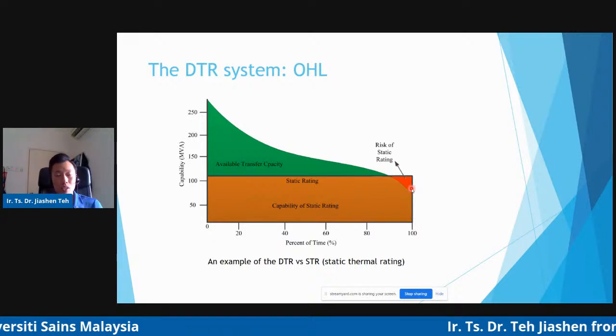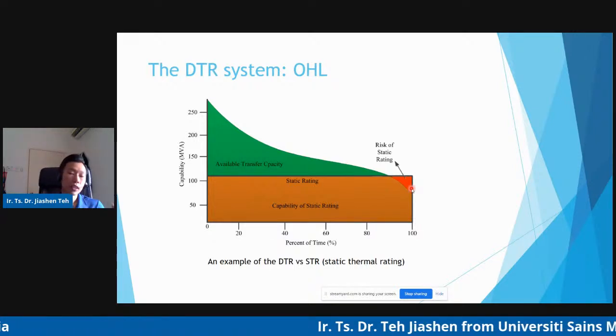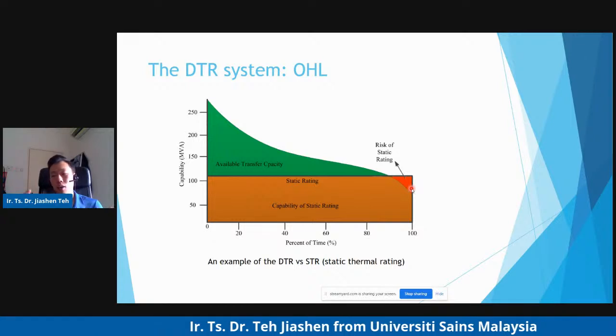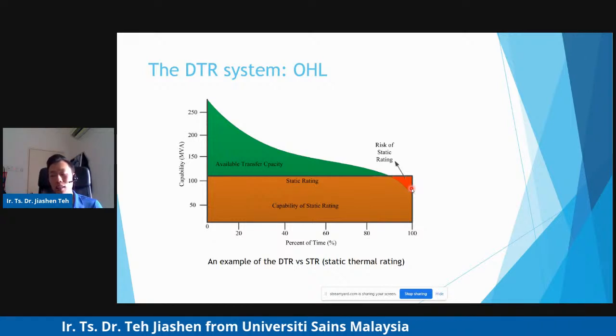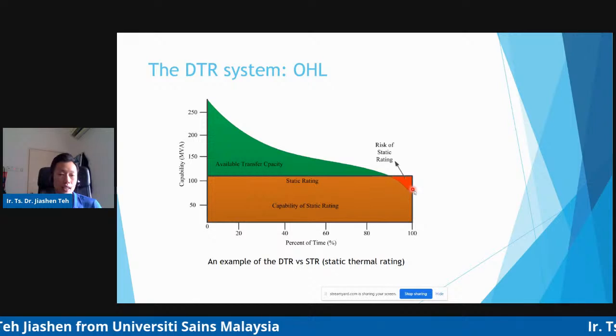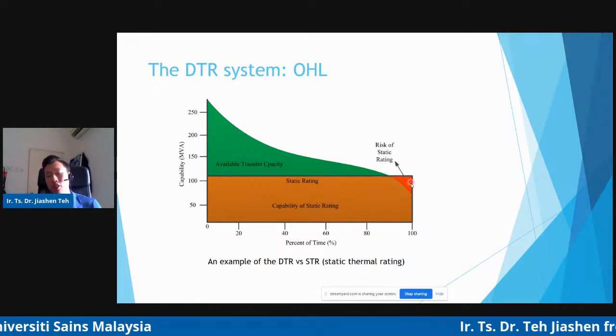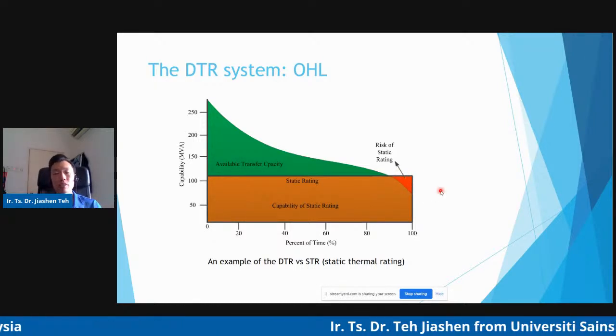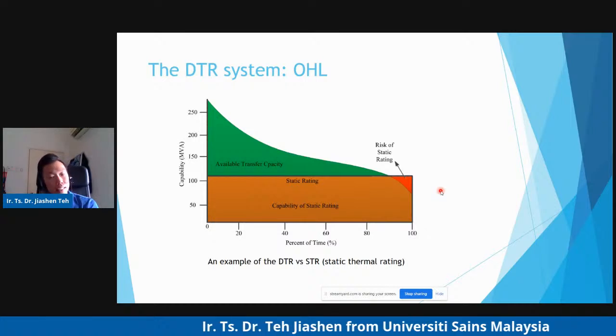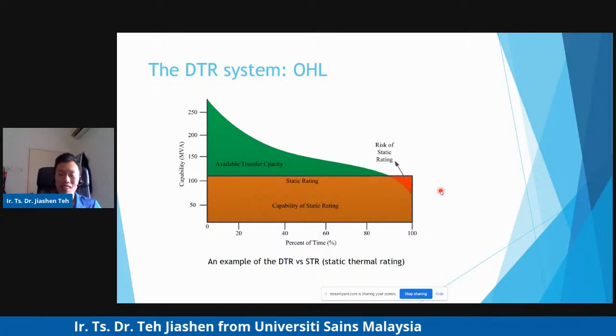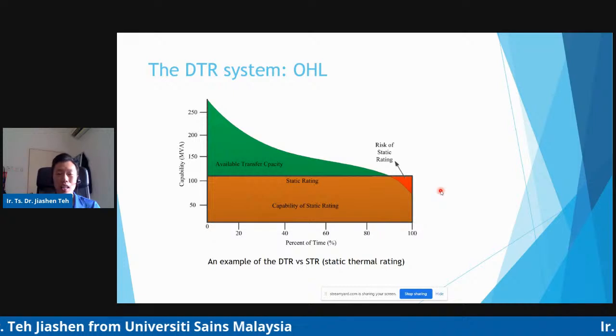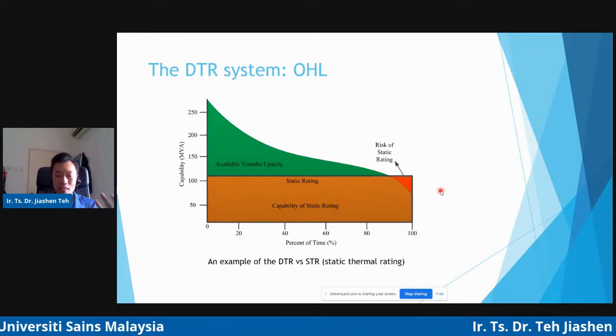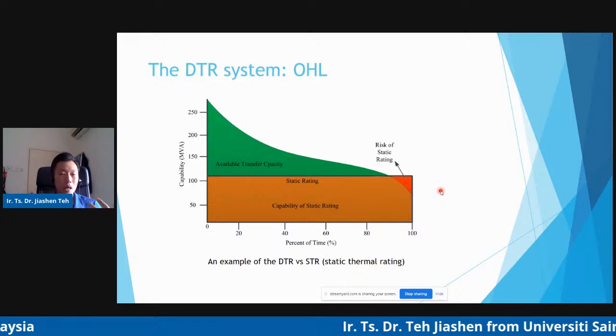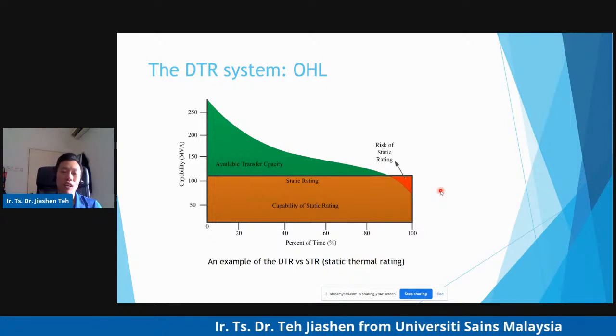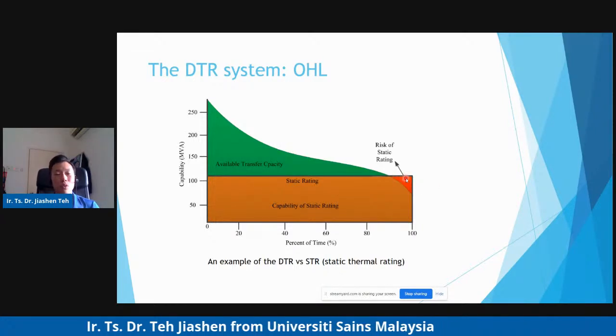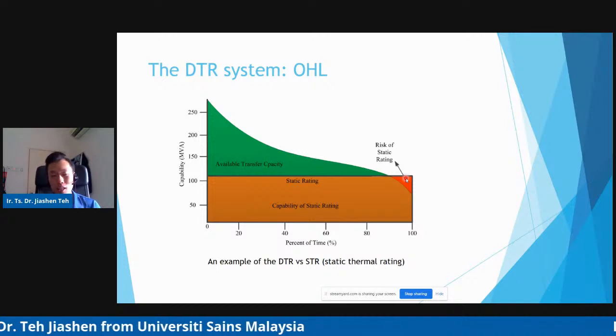With DTR, we not only benefit from a higher rating, we also avoid rating the line when the actual rating is lower, such as represented in this red region. So DTR avoids overheating the line and also avoids wasting the actual capacity of the line. STR is simple and less costly, but it bears the risk of overloading and also underutilizing the transmission line.